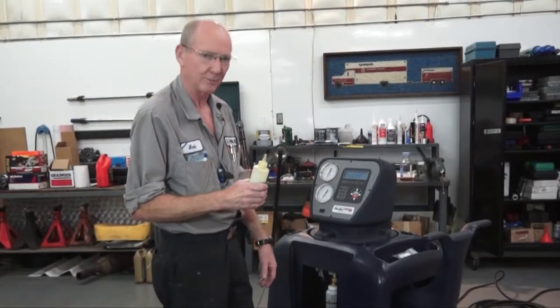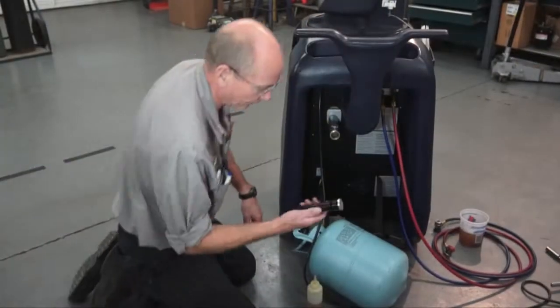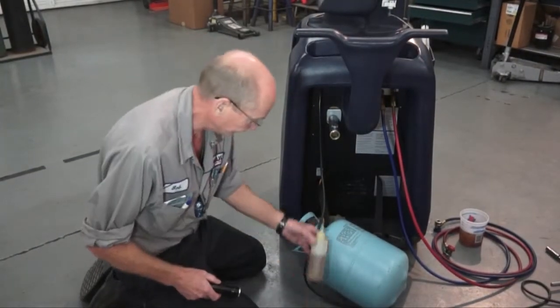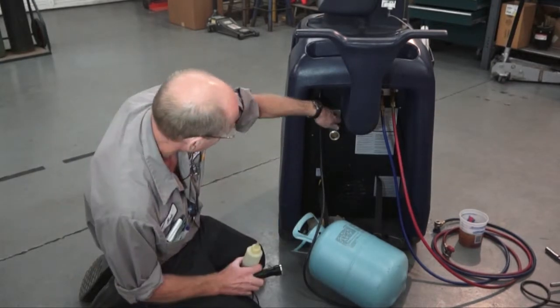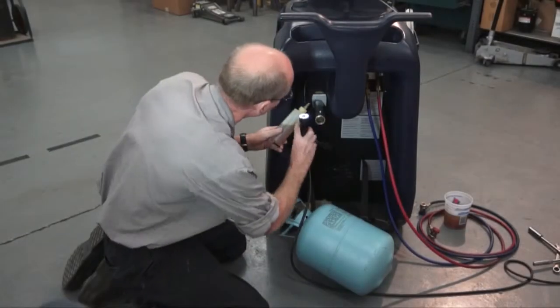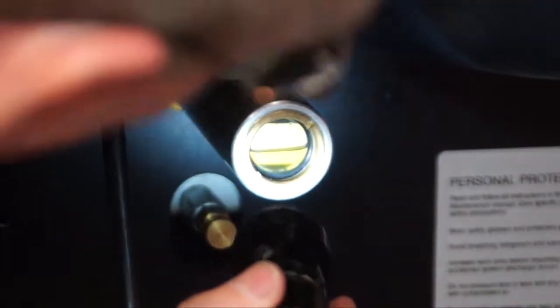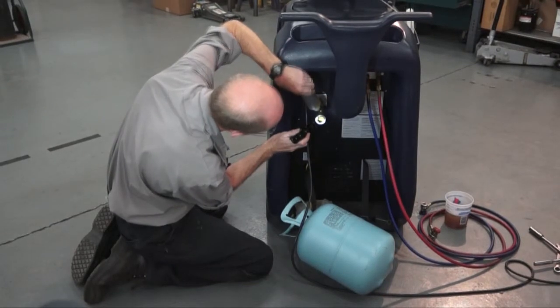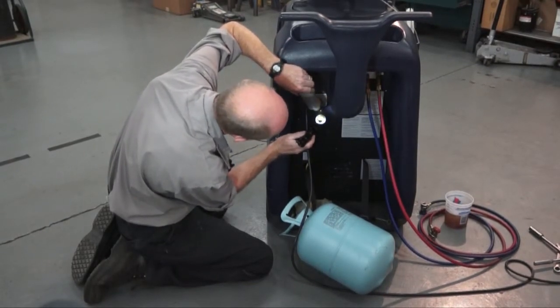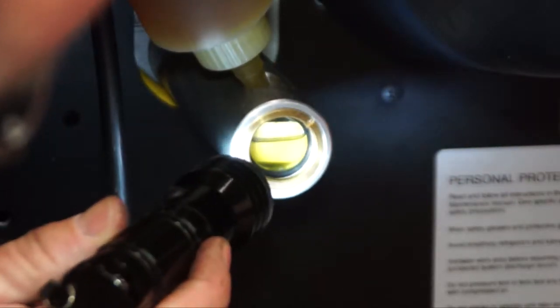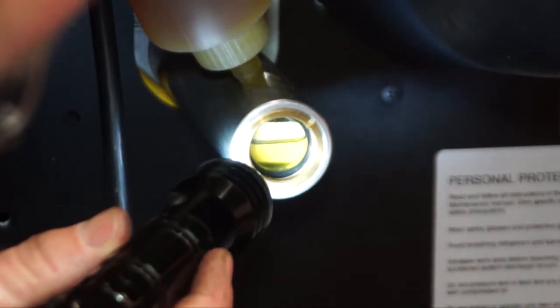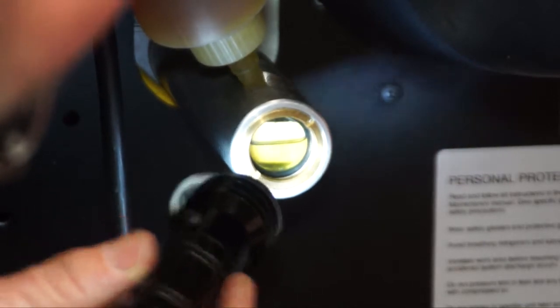It's going to perform a vacuum. So again, I'm going to let that run for about 2 minutes to circulate the oil. I have a little LED flashlight. I'm getting ready to put the remainder of the oil in. It's run for about 2 minutes. I'm going to pull the cap off and fill it, watching that oil level as I'm slowly squeezing this in there. You can squeeze it in, get it up to full, back it off. You want to continue to feed it the oil and then wait a few seconds, and you'll see it come back down to even, knowing that it's a 16 ounce system, and that's what I took out of it. I'm going to continue to put oil in it.